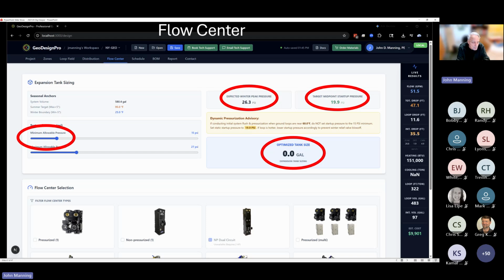Now, if you really want to tighten up the range of pressure, let's say you only want 1 psi of fluctuation. Well, then the program will tell you you need an expansion tank that can accommodate 24.6 gallons of fluid. So you can size one that can handle that. And if you really want to dig deep into the engineering calculations behind all this, I would suggest looking at a video we created. It's on our Phoenix Energy Supply YouTube channel. So I'd encourage you to look at that.